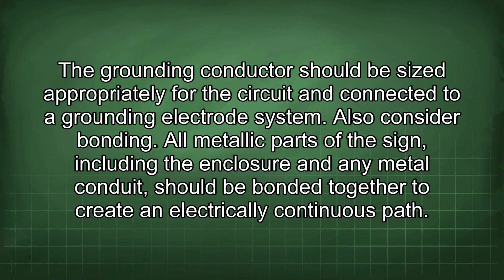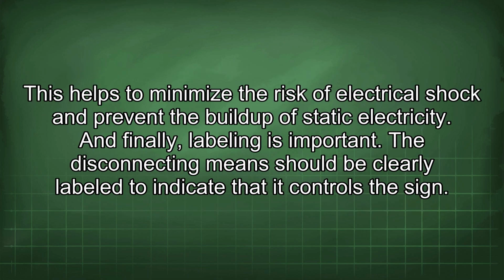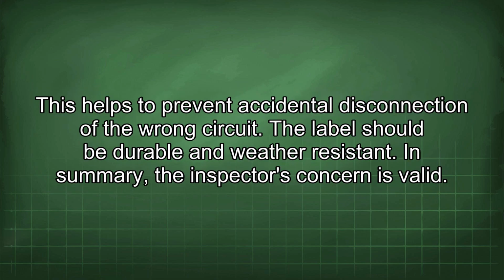Also consider bonding. All metallic parts of the sign, including the enclosure and any metal conduit, should be bonded together to create an electrically continuous path. This helps to minimize the risk of electrical shock and prevent the buildup of static electricity. And finally, labeling is important. The disconnecting means should be clearly labeled to indicate that it controls the sign. This helps to prevent accidental disconnection of the wrong circuit. The label should be durable and weather resistant.